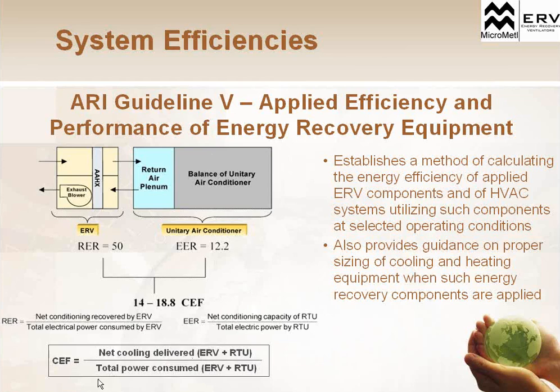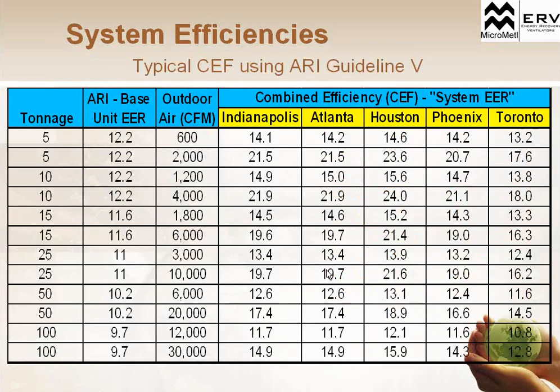a CEF value. So it's basically the net cooling delivered divided by the total power consumed. So it's the net cooling of the energy recovery unit plus what the rooftop unit or HVAC system has to do, divided by how much power is actually used. And if we're preheating or pre-cooling that air with the ERV, that's obviously less compression and less electrical usage we have in the HVAC system. So inherently we'll get higher EER values with those combined systems.